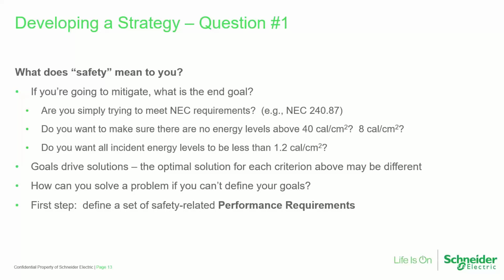Or maybe we want to bring it below 8 calories so we don't have to wear the full-blown arc flash suit. We've had some that say we want all incident energy levels, or at least anywhere that we can get them, to be less than 1.2 calories per centimeter squared. I will tell you, and if you looked into this in any detail, you know that this is true. The solutions that you need to get below 1.2 may be very different than what you need to get you below 40 calories per centimeter squared. To get you below 40, maybe all that you have to do is that setting optimization that we talked about, just intelligent selection of those settings. 1.2 is a different animal.